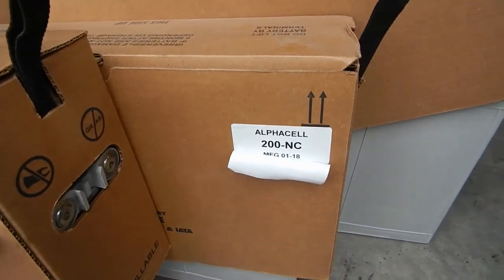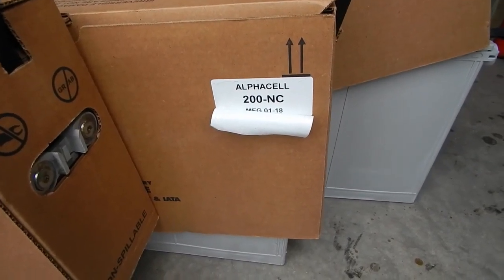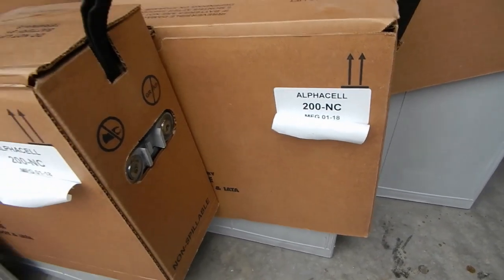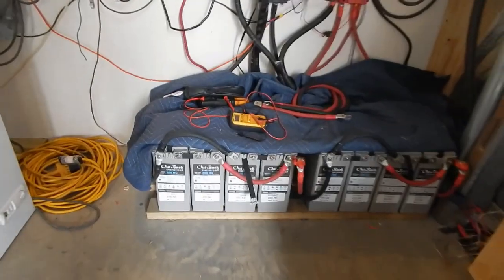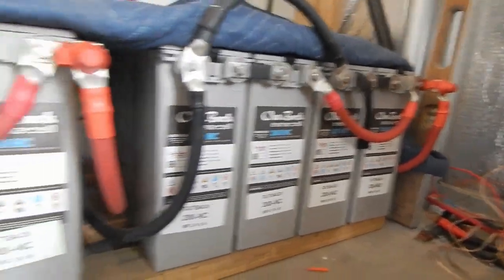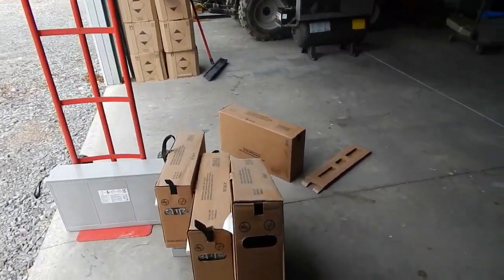They were covered in dust and stains, and I was told that's an Outback thing. So far I've contacted Outback and they've been super great — I sent them a bunch of pictures and they were shocked. They said I should have gotten new batteries. Over here on my battery bank, the batteries I commissioned on November 8th are all manufactured 01/18. Until this gets resolved, I'm not hooking up these batteries — I didn't buy 16-month-old batteries.